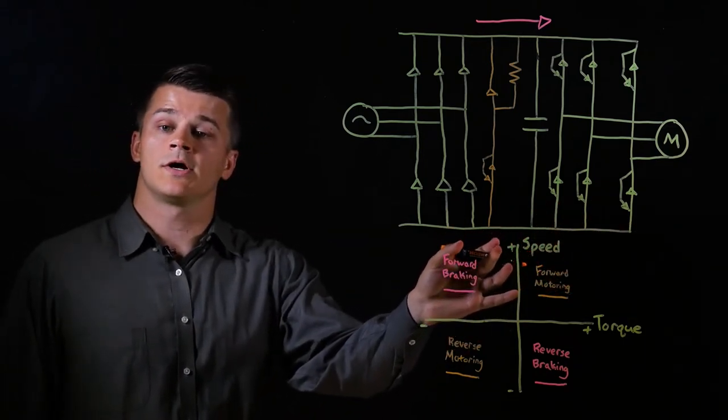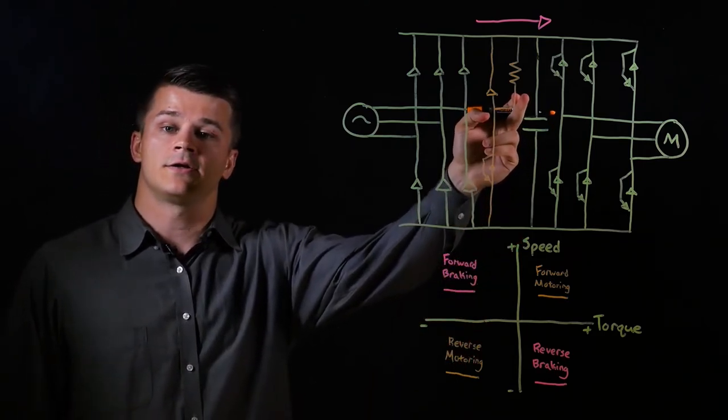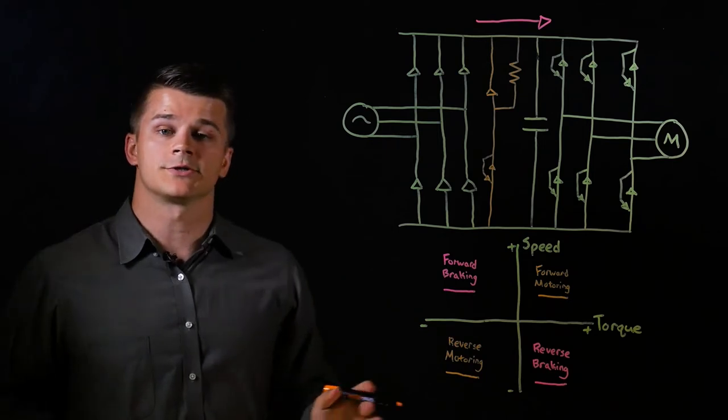How the braking resistor circuit works is the transistor switches on once the voltage reaches a certain level, and then the excess energy is dissipated across the resistor as thermal energy or heat.